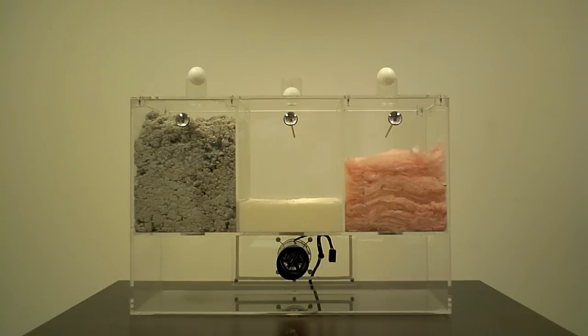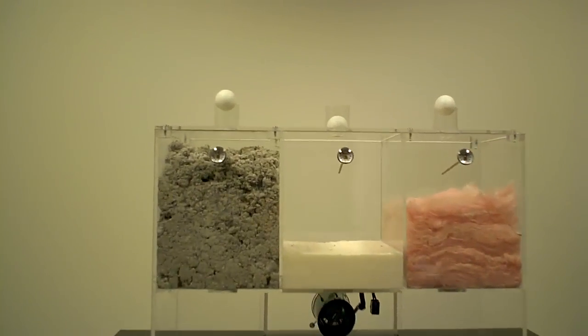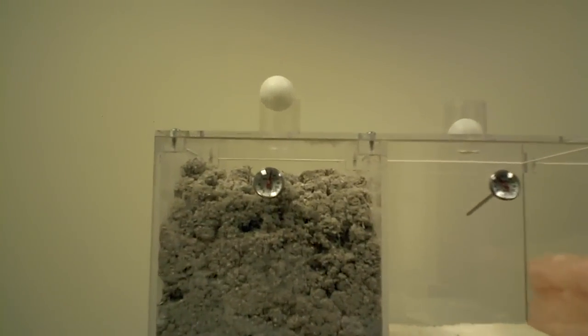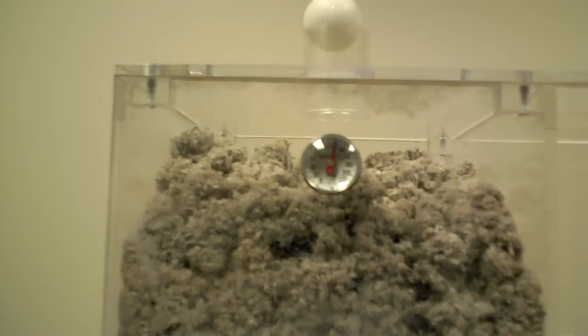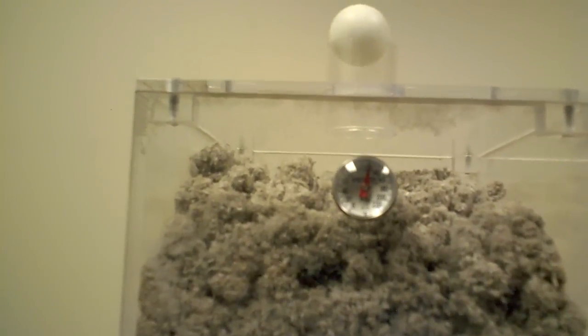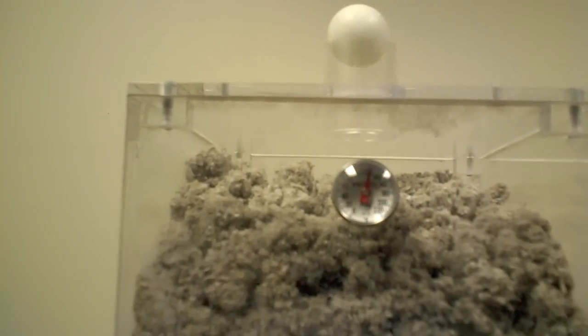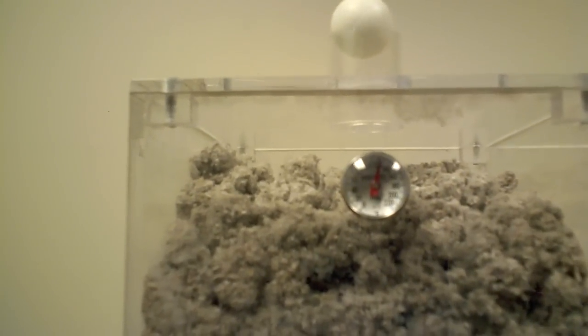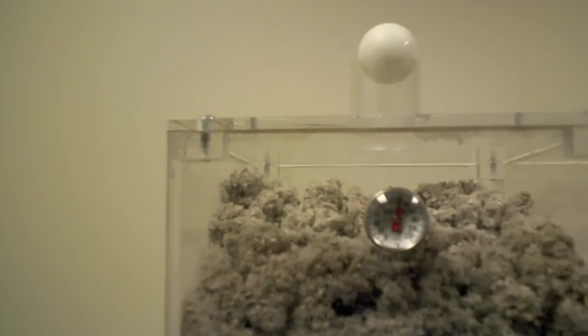Now, as we move a little closer to each of the three chambers, we can take a look at how to disprove the myth that more R-value is better. As we come up close here on this cellulose insulation, we can see that in the chamber, currently, the temperature is approximately 120 degrees Fahrenheit. This is with an R-value of 26.